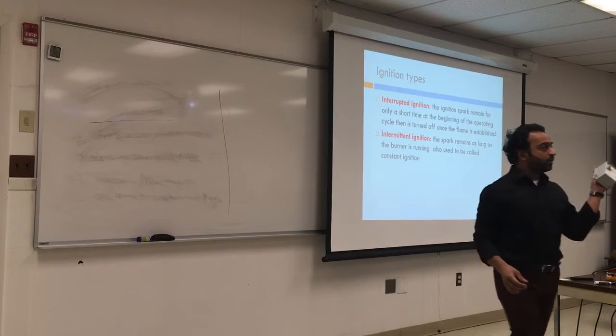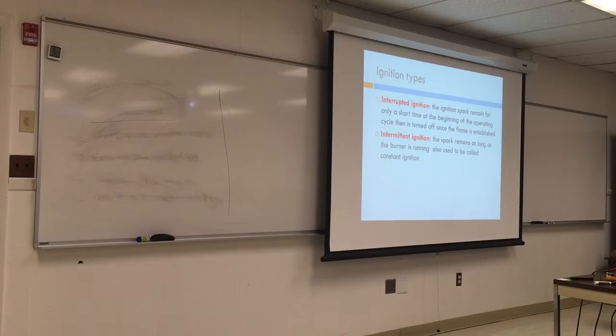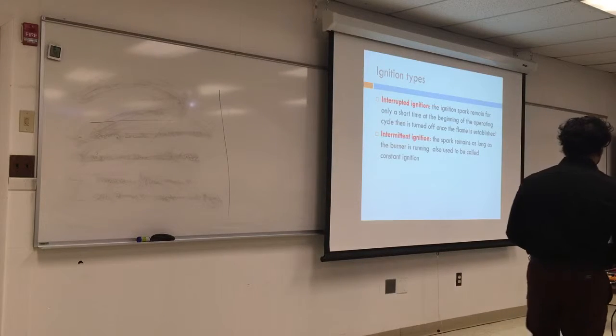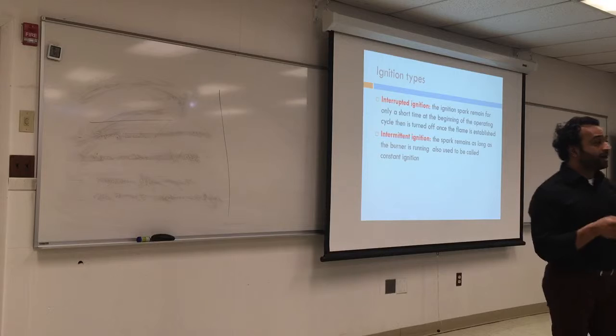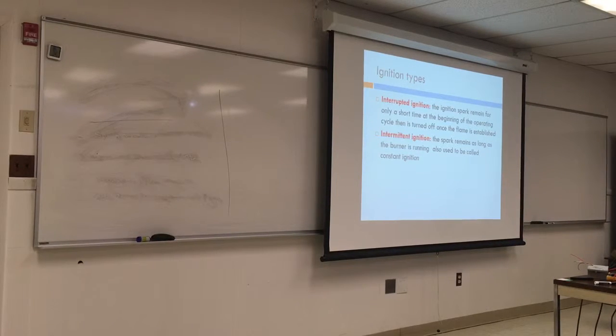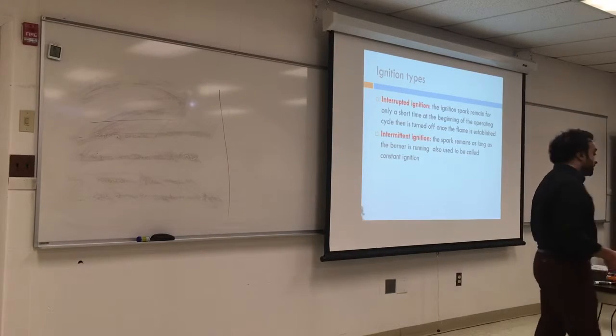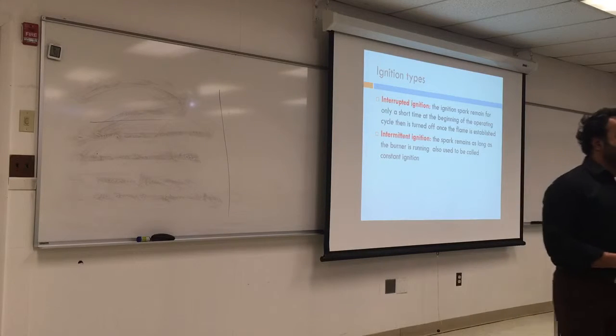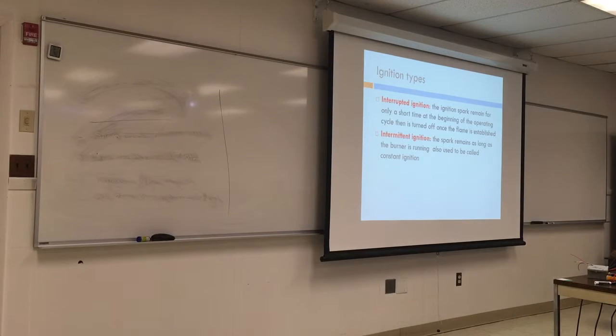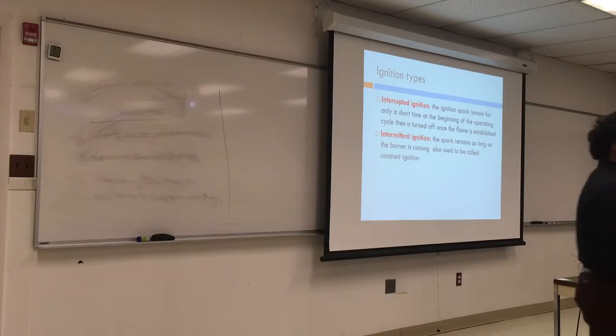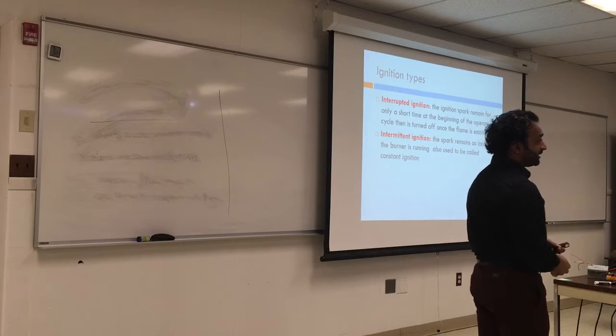So this is the old primary control, and there's only one wire that powers everything. This powers the motor, this powers the transformer, and the oil valve, which means that the ignition is on the entire time. It's good for old boilers because if you have ignition the whole time, you have a constant source of heat to ignite the oil. However, it's not a good thing because it will cover up a lot of issues with the smoke and also with wasted energy. The igniter consumes around 75 watts, which is a lot.